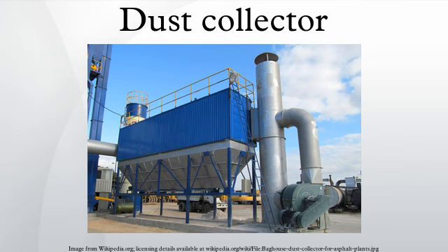Fan and motor. The fan and motor system supplies mechanical energy to move contaminated air from the dust-producing source to a dust collector. Types of fans. There are two main kinds of industrial fans: centrifugal fans and axial flow fans. Centrifugal fans consist of a wheel or a rotor mounted on a shaft that rotates in a scroll-shaped housing. Air enters at the eye of the rotor, makes a right-angle turn, and is forced through the blades of the rotor by centrifugal force into the scroll-shaped housing.